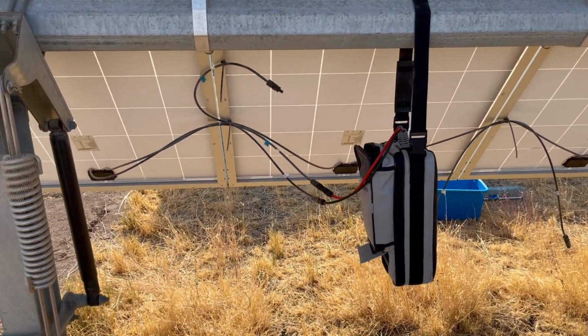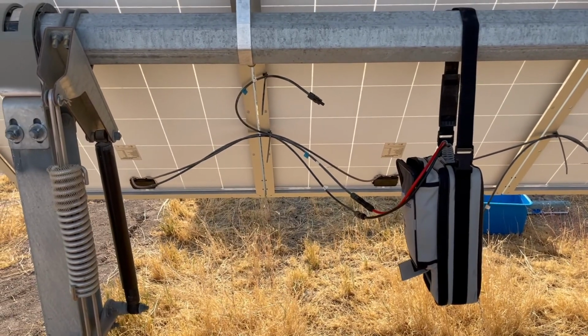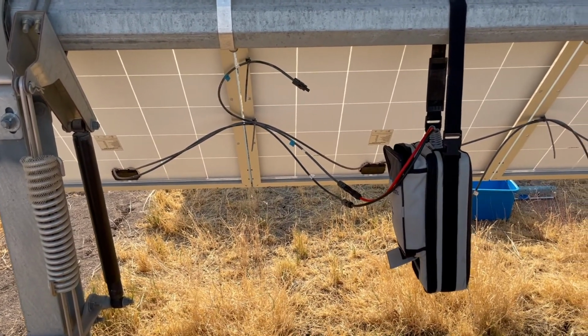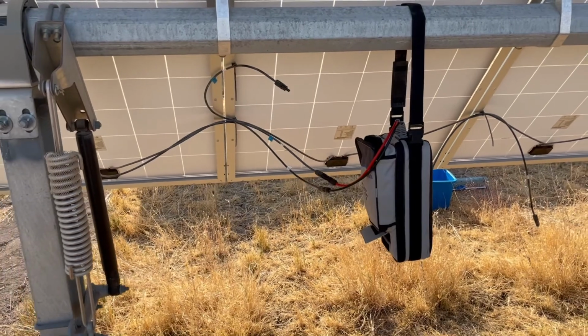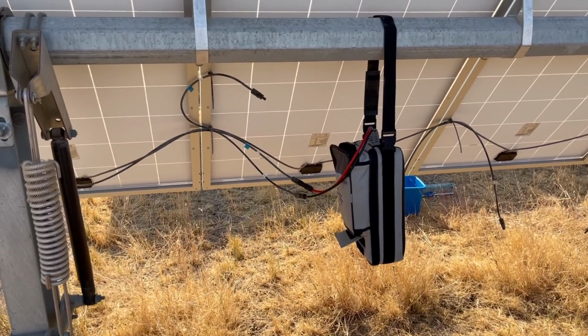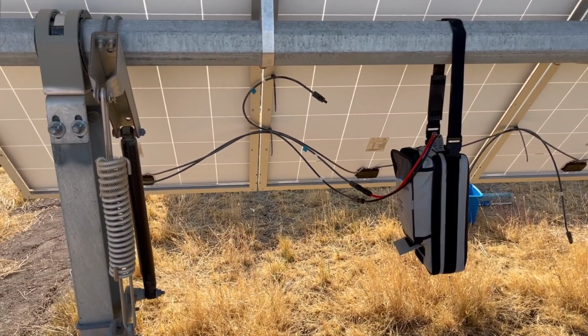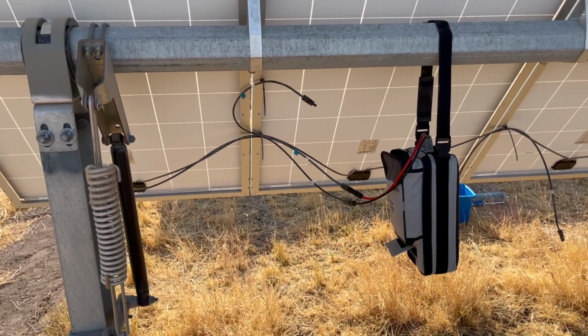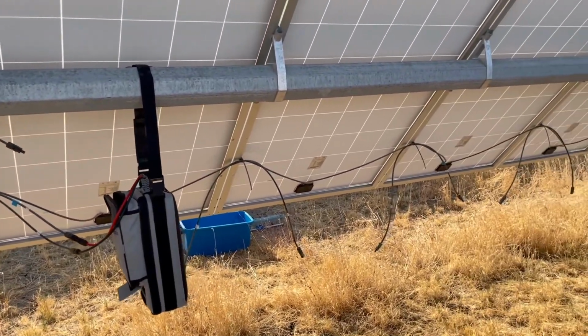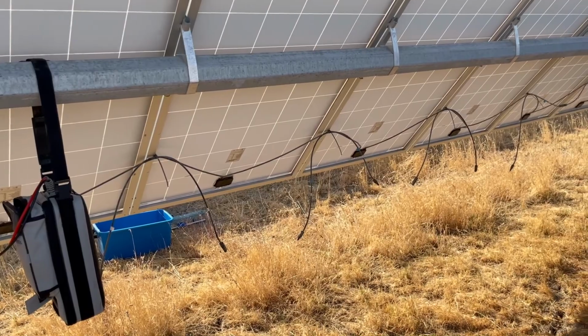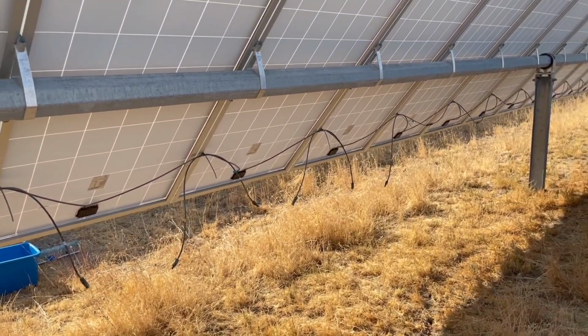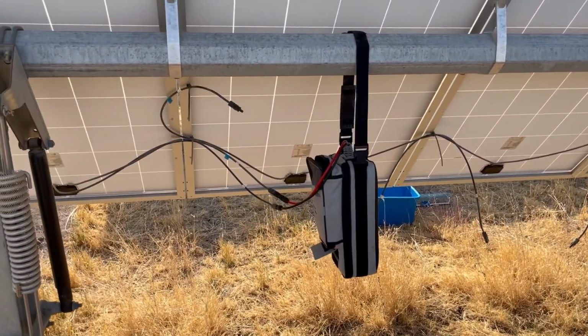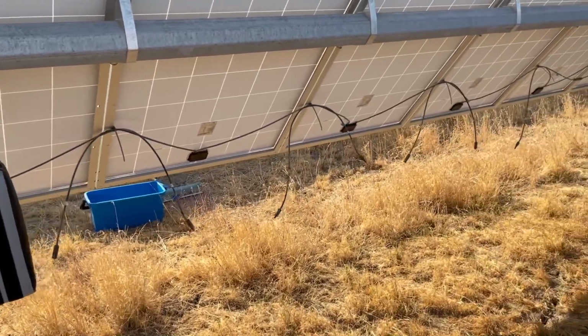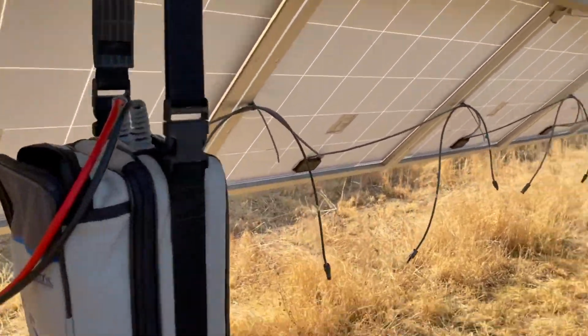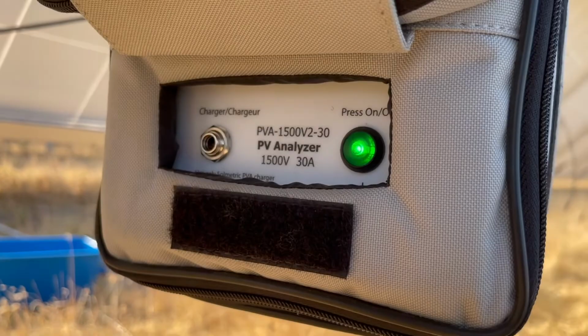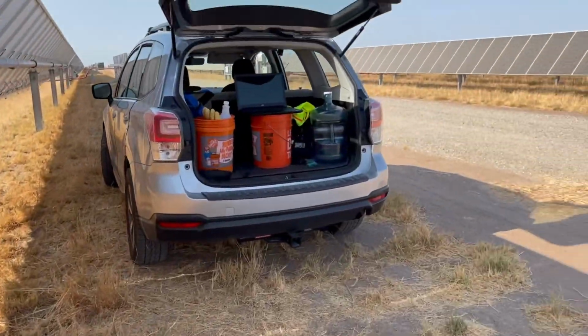Since the J boxes are on the downside, it's morning, and they're on the low side, the way the instrument hangs with the strap, I can get the first 2 modules without moving that instrument. Then I just have to pop over one bay and test the 3rd, 4th and 5th modules. It should take about 15 minutes. I've turned them both on. They're solid lights. It looks like they're acquired.